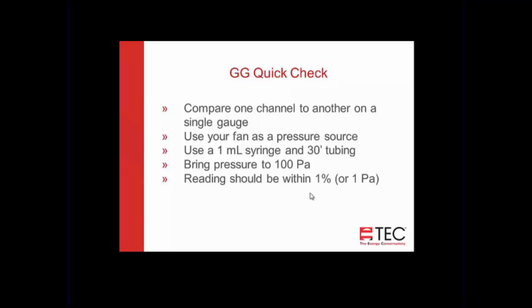Another thing you can do is use your fan, either blower or duct blaster fan, uncap it, run the tubing from the tap on the fan to a T and connect it to input and reference on your gauge, and turn on, leave it in pressure mode, PR, so you're reading pascals on both channels, and turn up that fan.